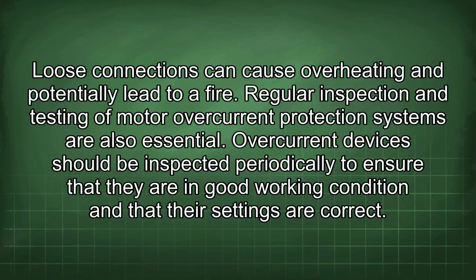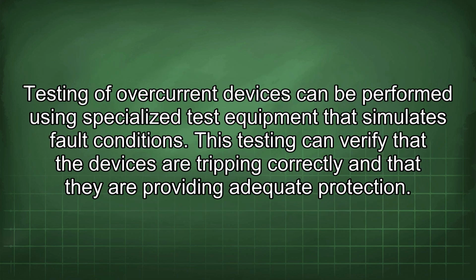Regular inspection and testing of motor overcurrent protection systems are also essential. Overcurrent devices should be inspected periodically to ensure that they are in good working condition and that the settings are correct. Testing of overcurrent devices can be performed using specialized test equipment that simulates fault conditions. This testing can verify that the devices are tripping correctly and that they are providing adequate protection.